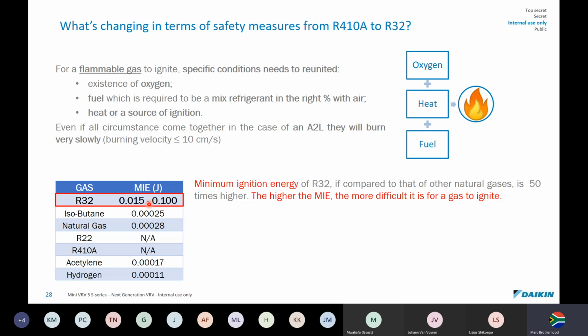And if we look at the gas, the MIE, which is the minimum ignition energy, that's rated in joules. R32, compared to other natural gases, is 50 times higher. So the higher the minimum ignition energy, the harder it is for the gas to burn. And here you can see these numbers are much higher. Butane, very explosive natural gas that you cook on, your gas bottles. Acetylene, also very explosive. And hydrogen, too, super explosive. R22 and 410 don't apply because they don't burn. But you can see the higher the numbers, the less that it burns.